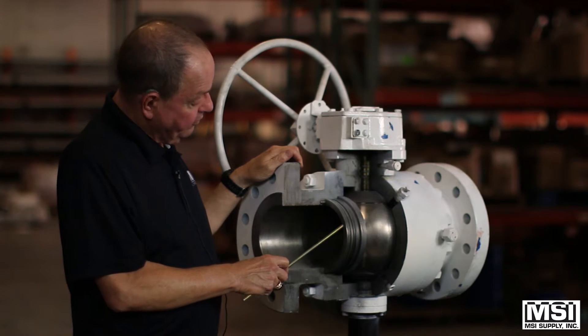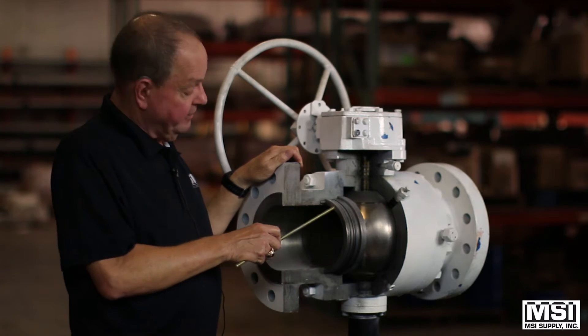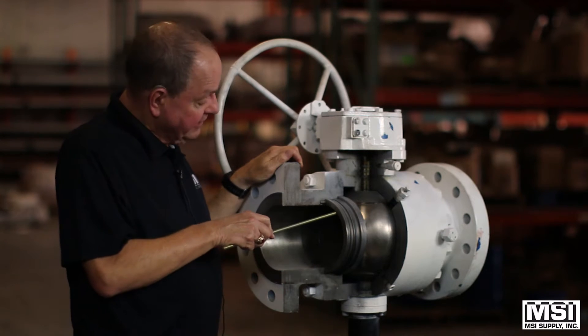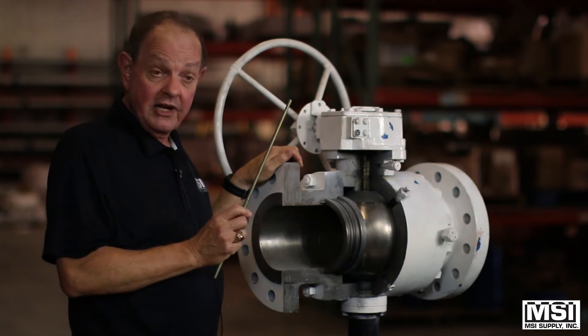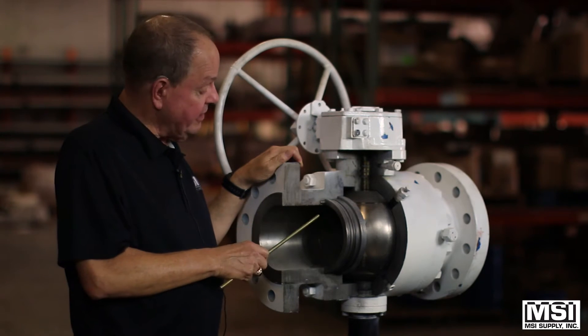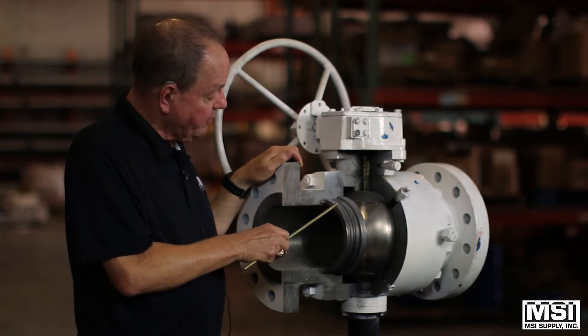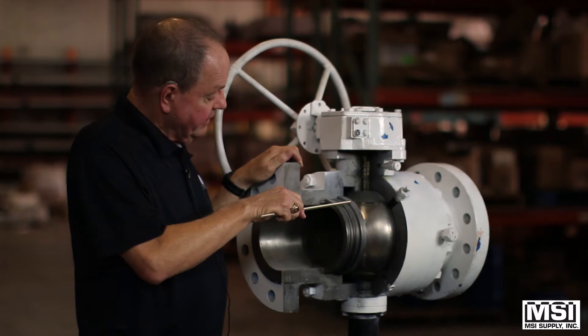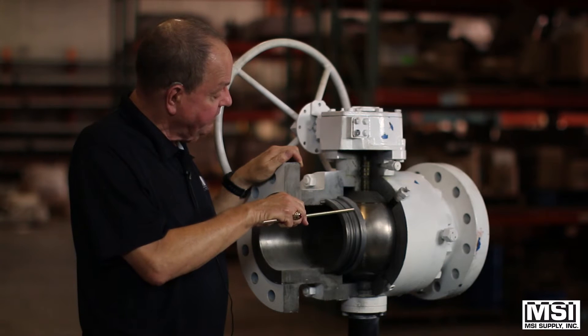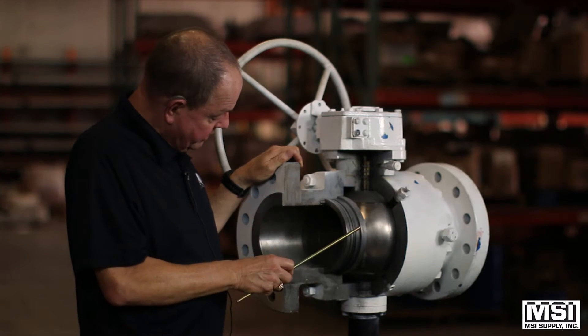For low pressure, when there's not much flow, there's a spring all around these seats that gives you a seal. When there's high pressure, the seal actually helps the springs to seal. The flow actually helps the springs to seal the valve up against the ball when it's closed.